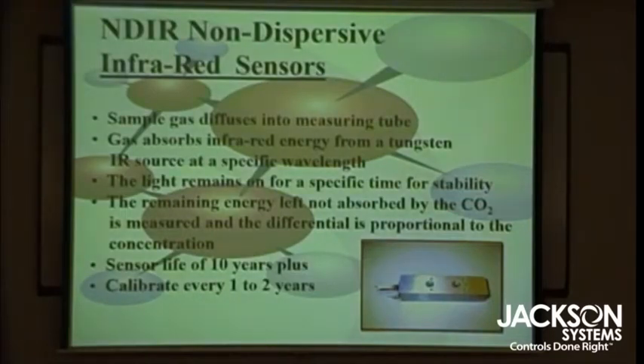Advantage of these sensors in industrial applications where you have a lot of methane or combustible gases, like in petroleum refineries, you always walk around, there's a smell of some gas. With catalytic sensors, you're replacing those maybe every 4 or 5 months. These will last 10 years.